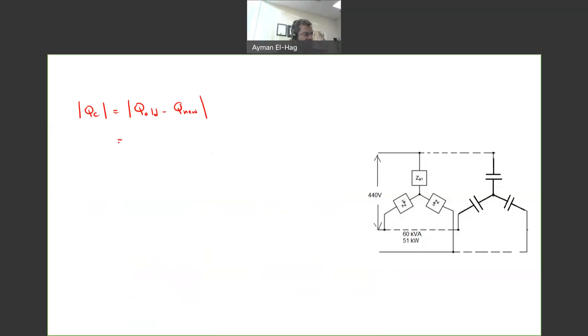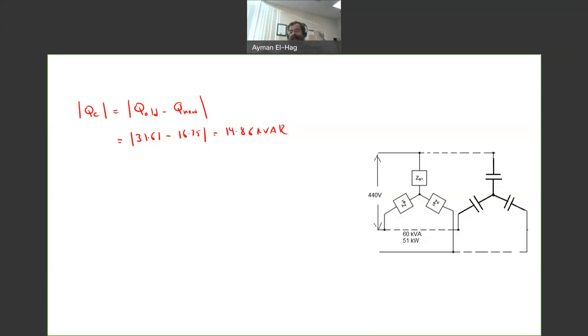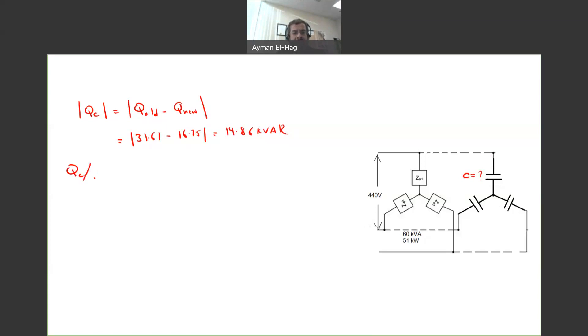From this we find the reactive power supplied by the capacitors: Q_C = Q_old − Q_new = 31.61 − 16.75 = 14.86 kVAR. This is the total Q supplied by the three capacitors in the three-phase capacitor bank. Since we want C per phase, Q_C per phase = 14.86 / 3 = 4.953 kVAR.